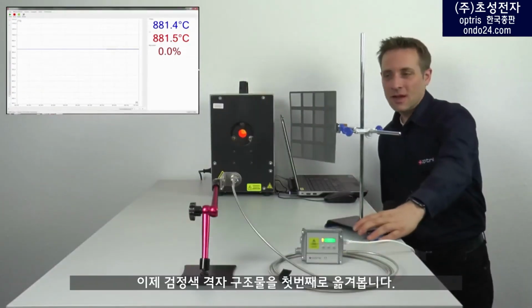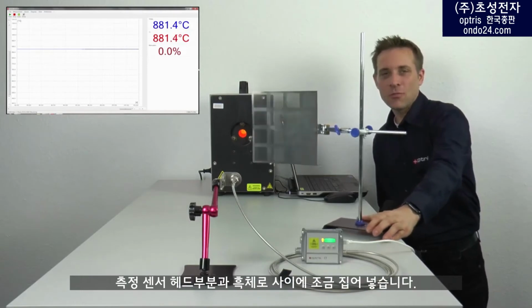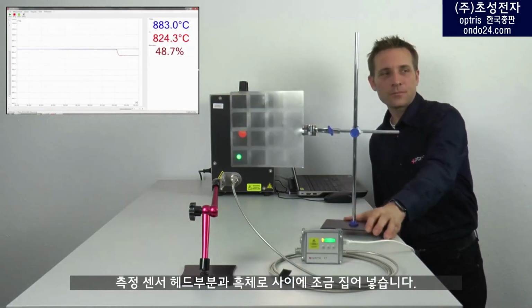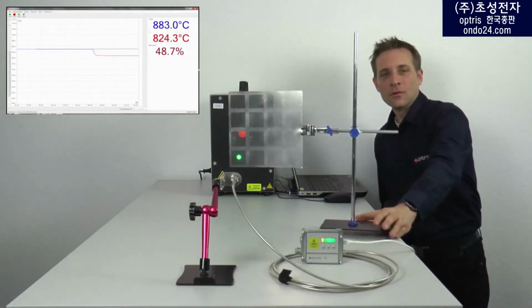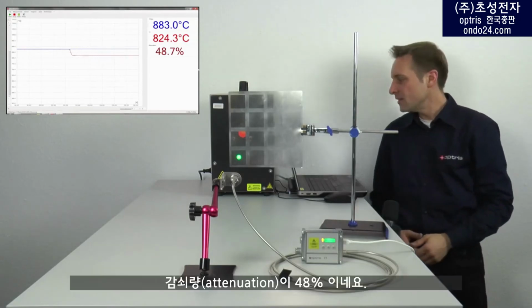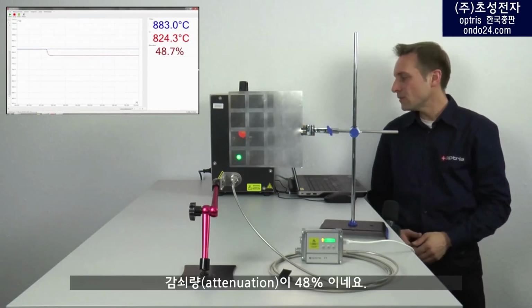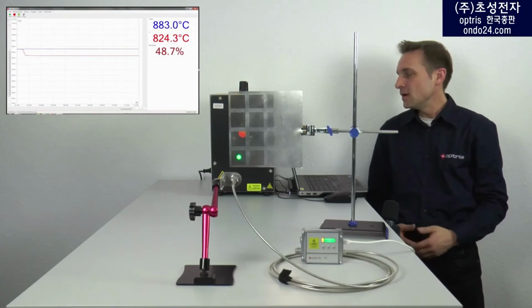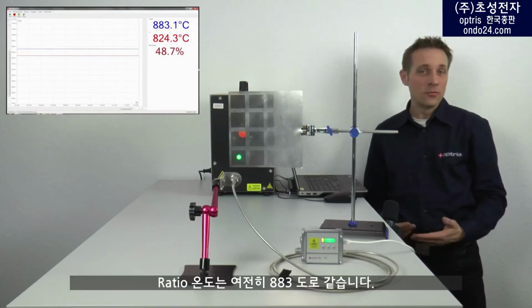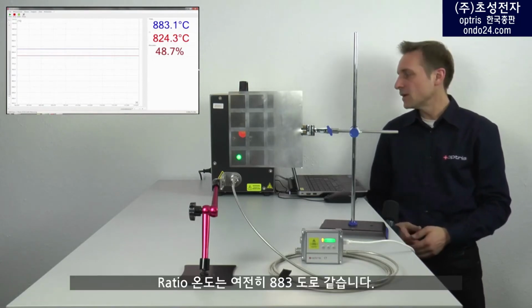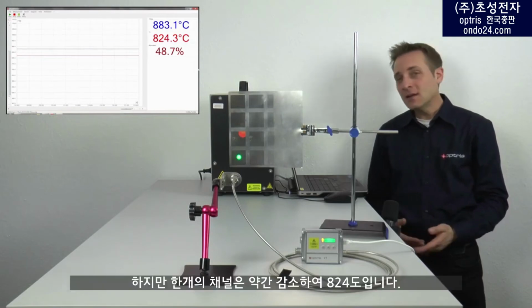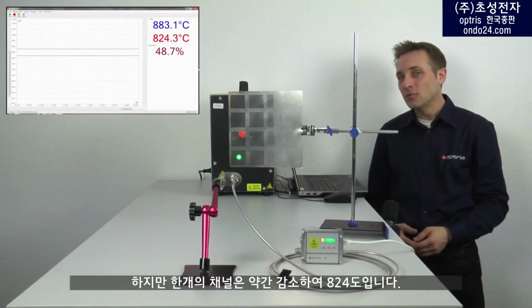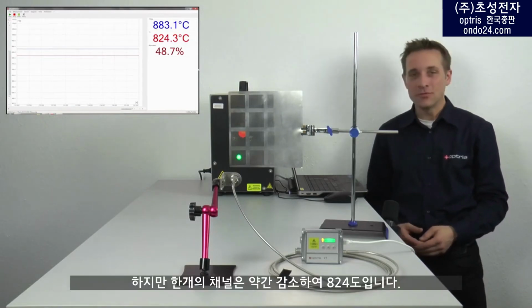Let's now move our first grid structure between sensor head and black body radiator, and find that we already have a 48% attenuation here. The ratio temperature is still correctly displayed at 883 degrees, but the one-channel temperature has gone down a little, now 824 degrees.